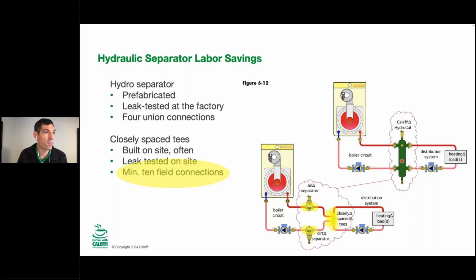Because if we're talking about 4 union connections for a hydro separator, where you can't really mess up the dimensions here, this is going to be the right size, and I'll go into more detail for what that actually means a little bit later. There are a lot of different things that can go wrong here, and with the best intentions, I've seen in the mechanical rooms that I've been to over the years, a lot of things can go wrong here. Spacing wise, there can be pieces omitted, or this is where you start to see 18 inches of space in between your closely spaced tees.